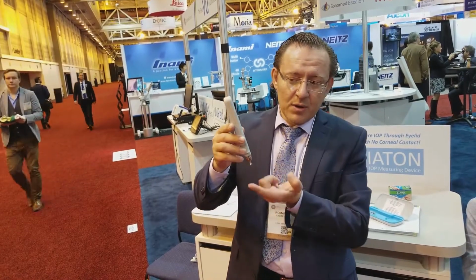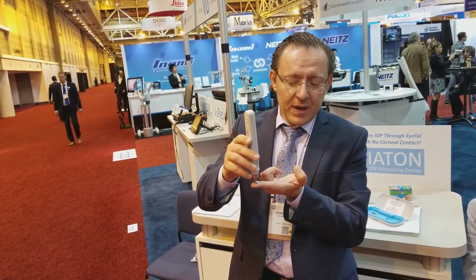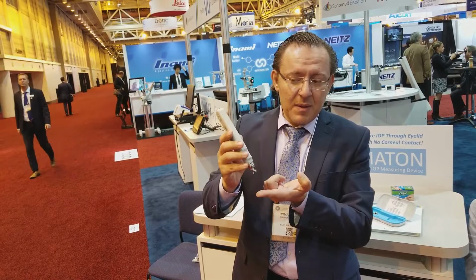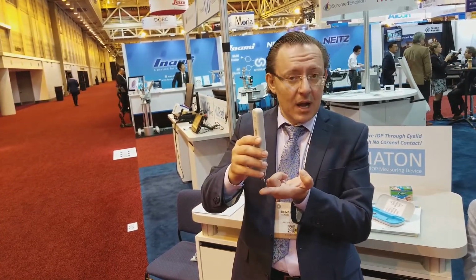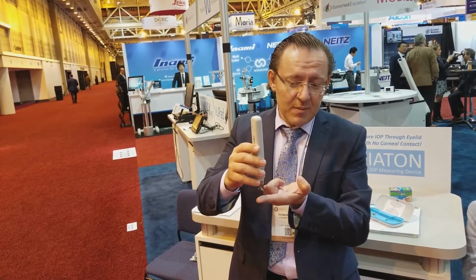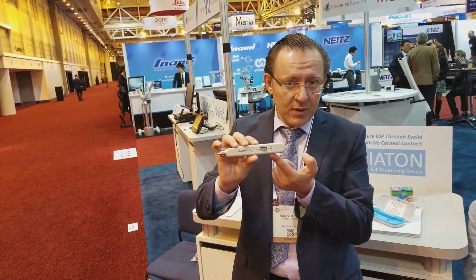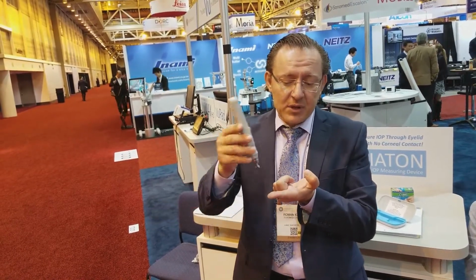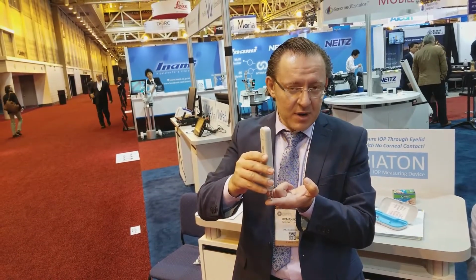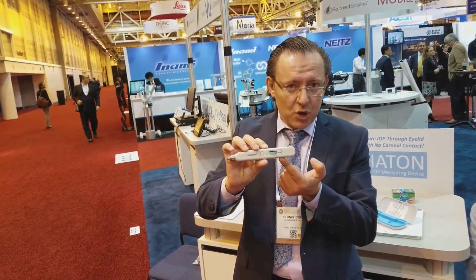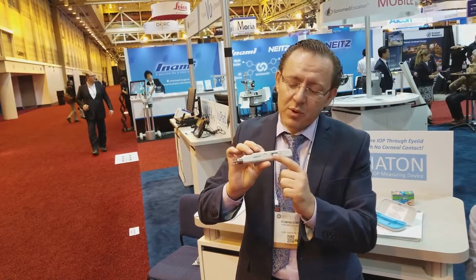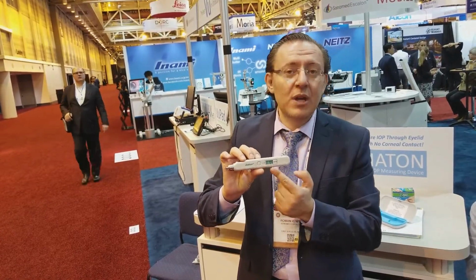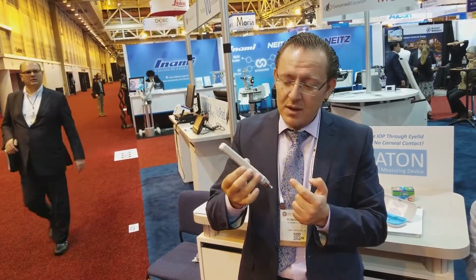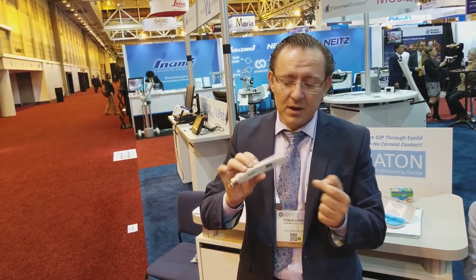Turn the device on, position on your finger, and the beeping sound will help you find a vertical position. At the correct position, the beeping will stop. Position, take a measurement. You'll get -1 on the display. Tilt it back for the second reading. Take a measurement. The device shows 2 on the display, at which point you press the center button. That will give you the average of the 2 readings. Okay? And I got a 4 on my finger. So now let's proceed to the eye.